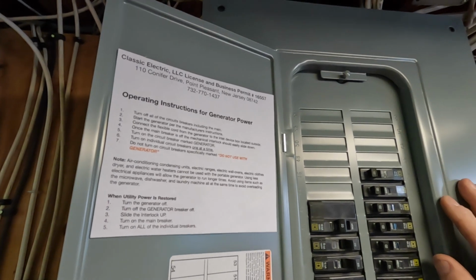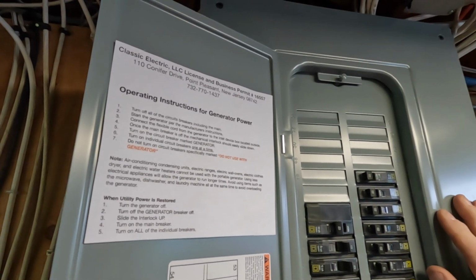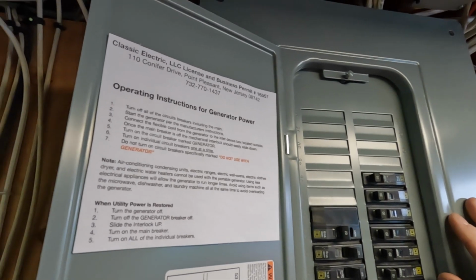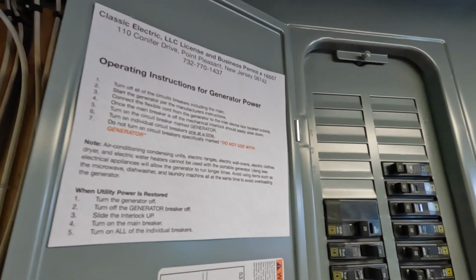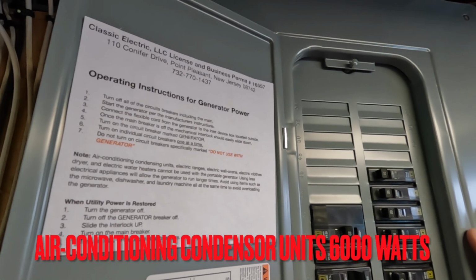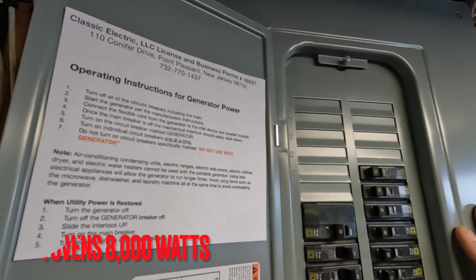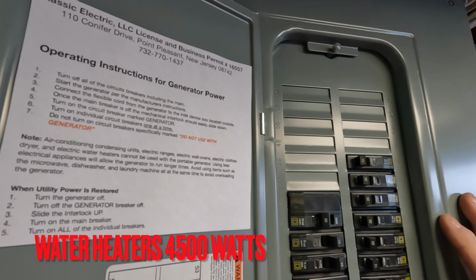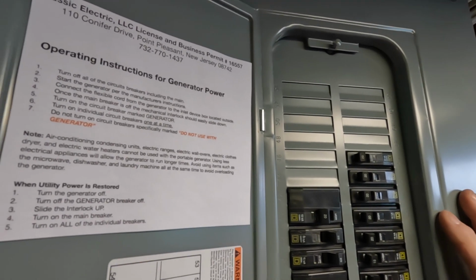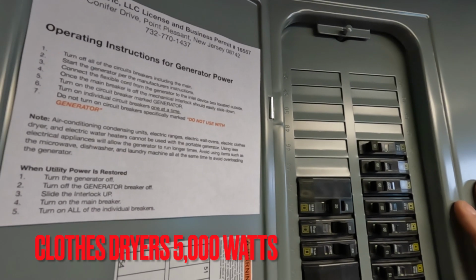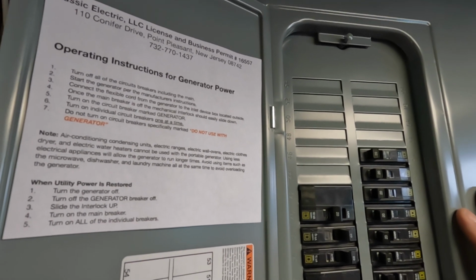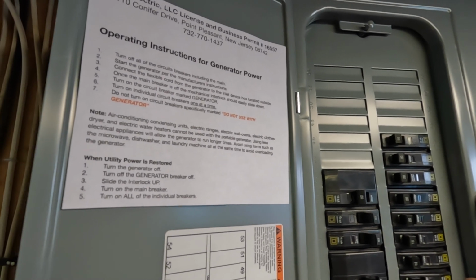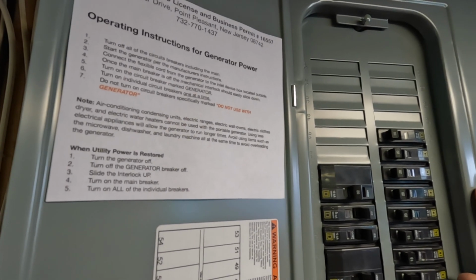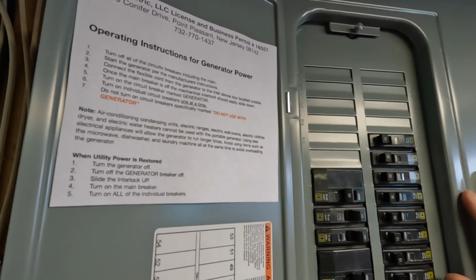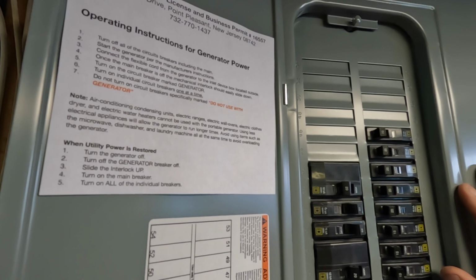Turn on the individual circuit breakers one at a time. Do not turn on any circuits that are specifically marked do not use with the generator. We're going to do that momentarily. Note the air conditioning condenser units, electric ranges, electric wall ovens, electric clothes dryers and electric water heaters cannot be used with the portable generator. Using fewer electrical appliances will allow the generator to run longer. Avoid using items such as the microwave, dishwasher, and laundry machine all at the same time to avoid overloading the generator. When the utility power is restored, we're going to turn off the generator breaker, slide the interlock up, turn the main breaker on, and then turn on all the individual breakers as well.